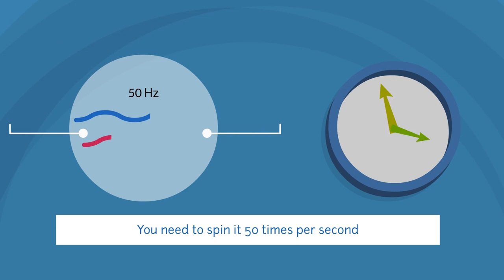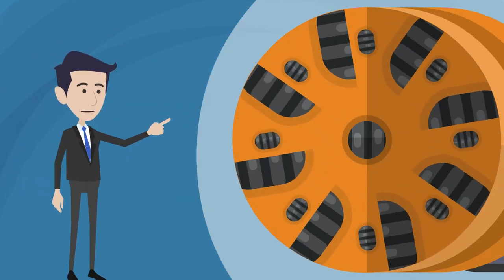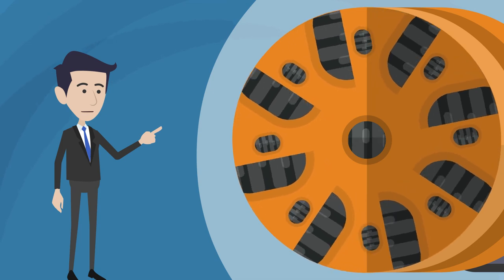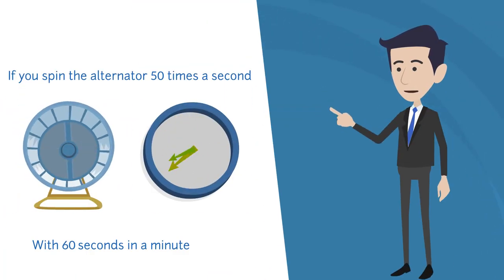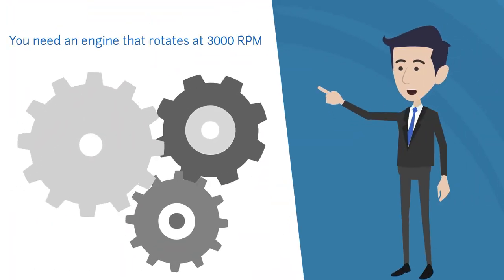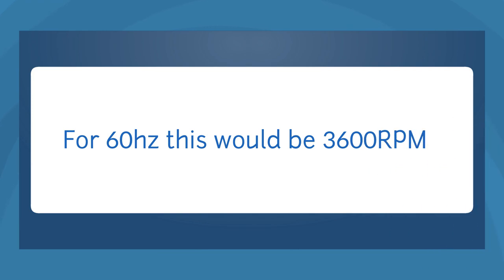Therefore, to create 50 Hz AC, you need to spin it 50 times per second. Engine revolutions are measured in RPM, or revolutions per minute. If you spin the alternator 50 times a second, with 60 seconds in a minute, you need an engine that rotates at 3000 RPM. For 60 Hz, this would be 3600 RPM.